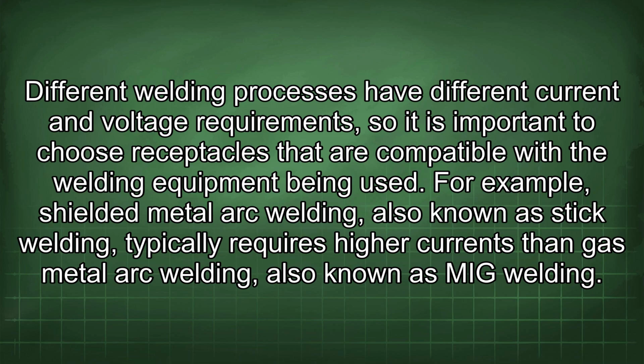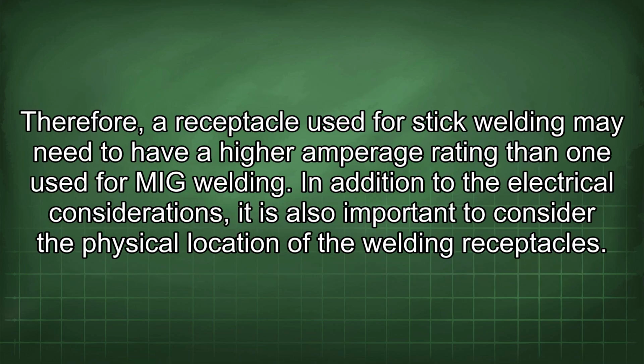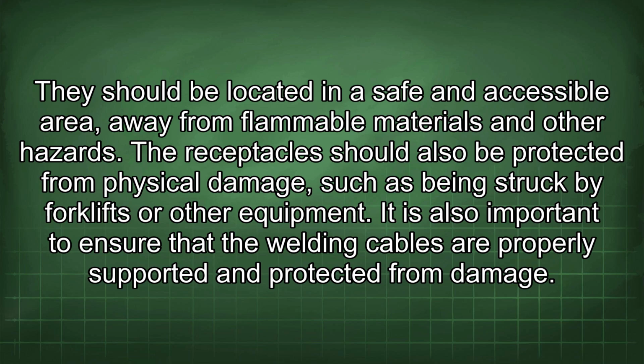For example, shielded metal arc welding, also known as stick welding, typically requires higher currents than gas metal arc welding, also known as MIG welding. Therefore, a receptacle used for stick welding may need to have a higher amperage rating than one used for MIG welding. In addition to the electrical considerations, it is also important to consider the physical location of the welding receptacles. They should be located in a safe and accessible area, away from flammable materials and other hazards. The receptacle should also be protected from physical damage, such as being struck by forklifts or other equipment.